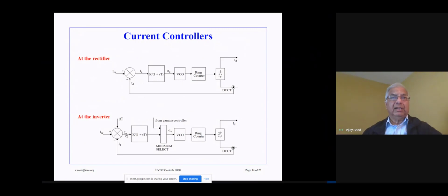So we generate an error signal. We go through a PI regulator again, two gains, and then we go into the voltage controlled oscillator and a ring counter to distribute the firing pulses to the converter. But at the inverter, we also have another controller. We have two controllers. This is the extinction angle controller. So in order to operate with two controllers over here, we have to select the minimum firing order based on the current control or the gamma controller. So we have a min select circuit, and then we select the firing order and then go through the system.